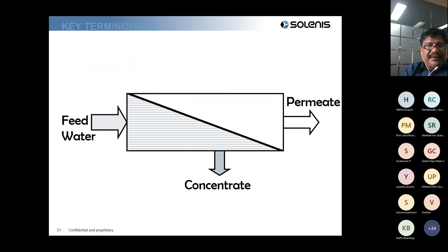98% will be rejected. So obviously, when we want to design an RO plant, I want to give you a thumb rule. For example, we have to design the number of membranes. The customer comes to me and tells me, I want a 25 cubic meter per hour RO plant. So will you design the plant from back to front or front to back? Can anybody tell me? As a chemical engineer, the customer has come to you and told you, I want a 25 cubic meter RO plant. So can anybody tell?